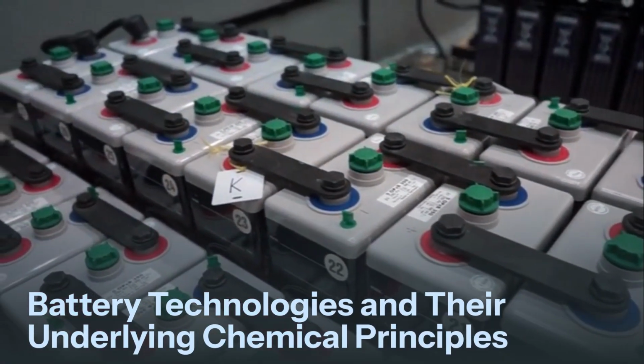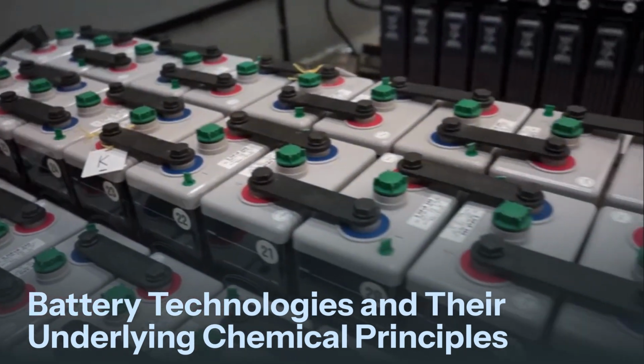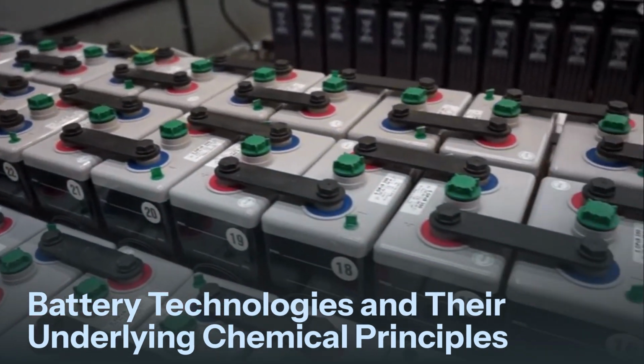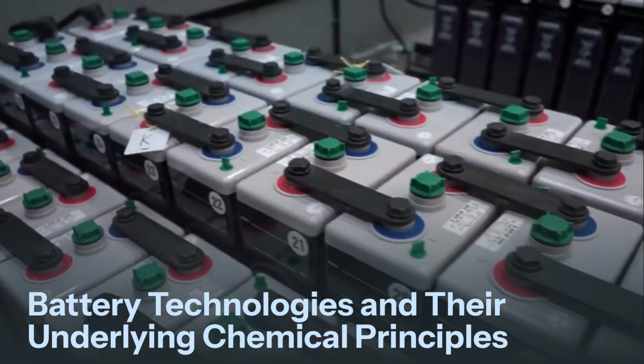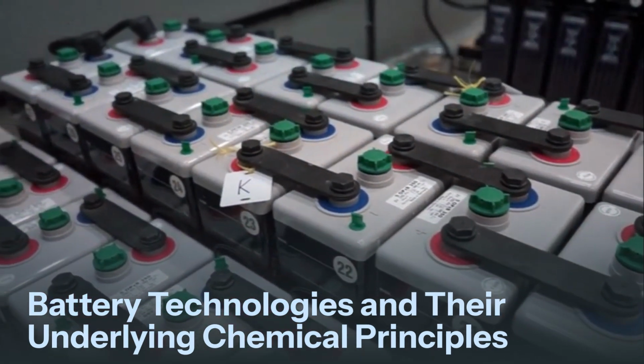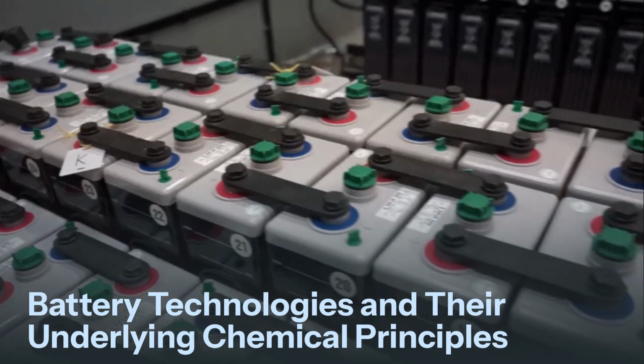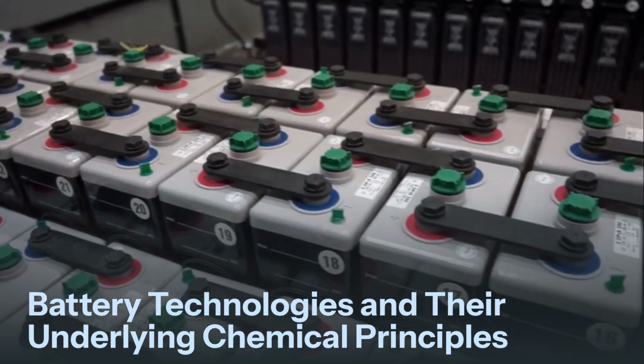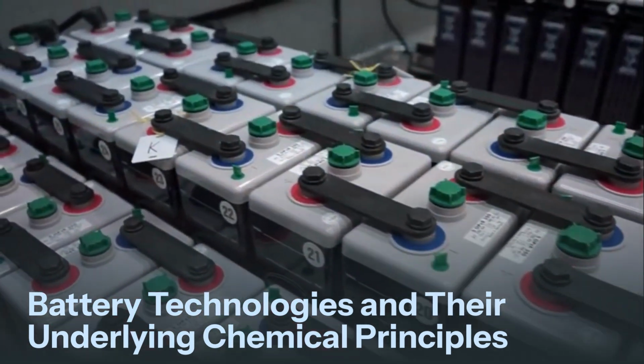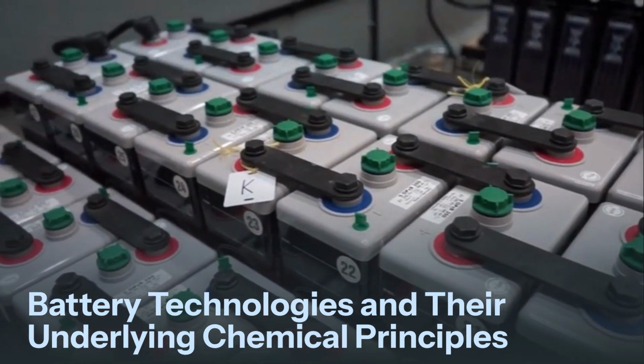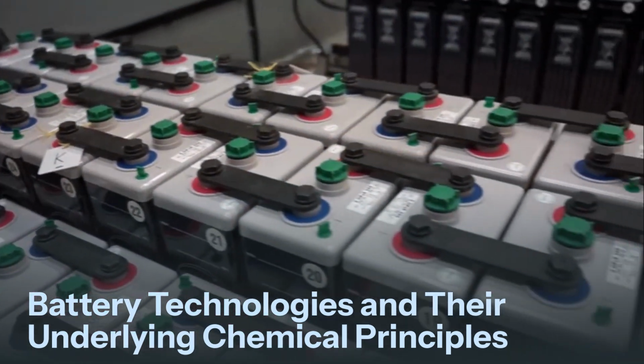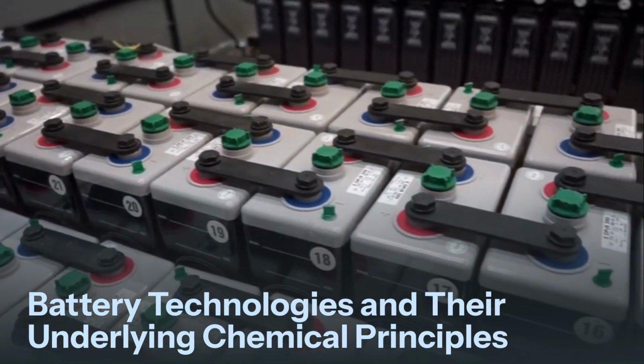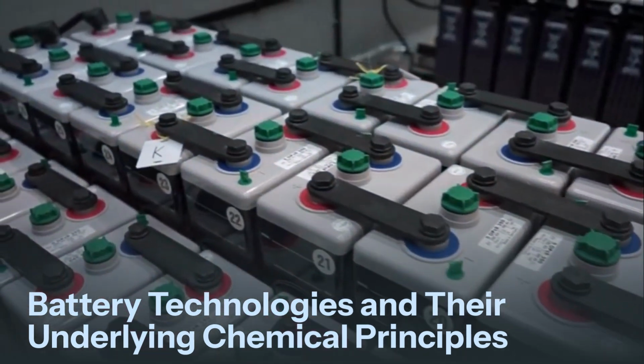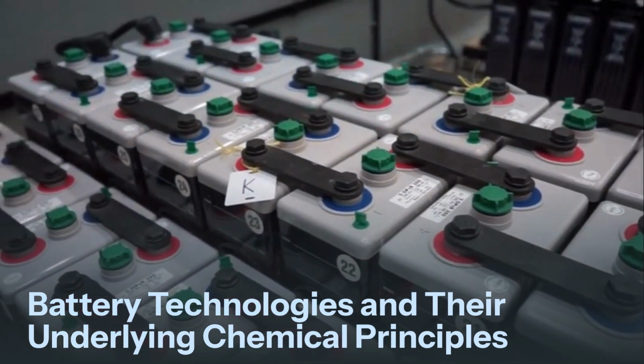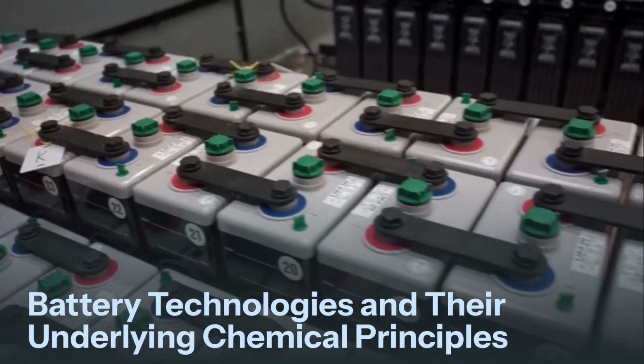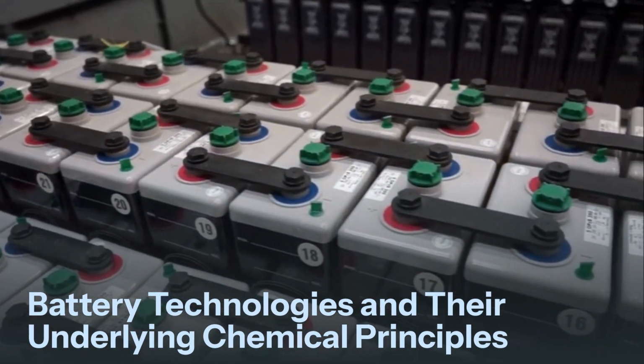Stationary battery systems are designed to provide reliable, long-duration energy storage and power continuity. Historically, they served as standby sources for control power, UPS, telecommunications, and substations. Today, large BESS installations also provide grid services, including frequency regulation, peak shaving, and renewable energy shifting. These use cases entail more frequent cycling, higher power levels, and greater integration with controls, protection, HVAC, and fire systems, thereby expanding both maintenance scope and safety exposure.